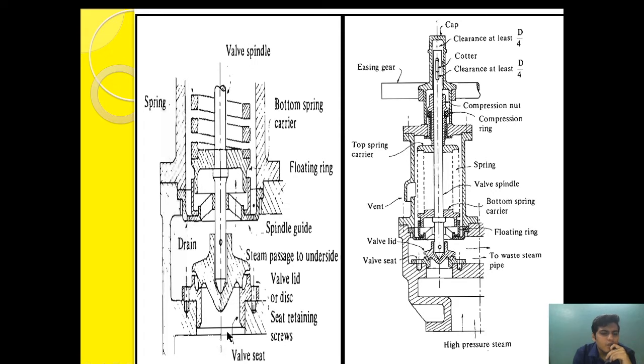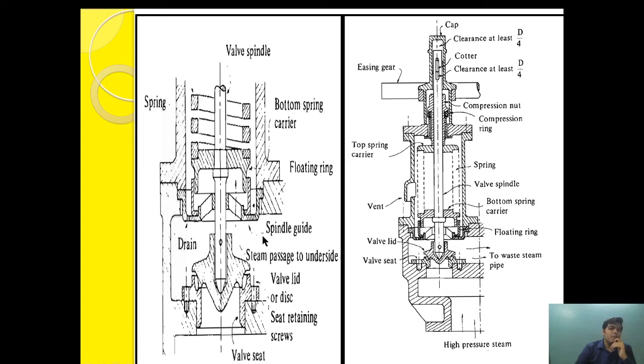When the valve is lifted, the steam pressure is acting directly on the lower spring carrier whenever steam is escaping. The steam escaping from the valve area is also acting on the lower spring carrier, so the spring is in direct contact with the escaping steam. As the pressure of the boiler increases, the temperature of the steam also increases.